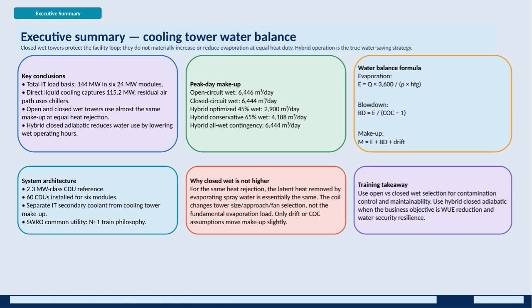When we talk about peak day makeup water, open circuit wet towers and closed circuit wet towers require roughly 6,445 cubic meters per day. Hybrid systems optimize this significantly, with water use dropping to as low as 2,900 cubic meters per day when operating at 45% wet. Even with conservative 65% wet operation, water use is still considerably lower than pure wet tower setups.